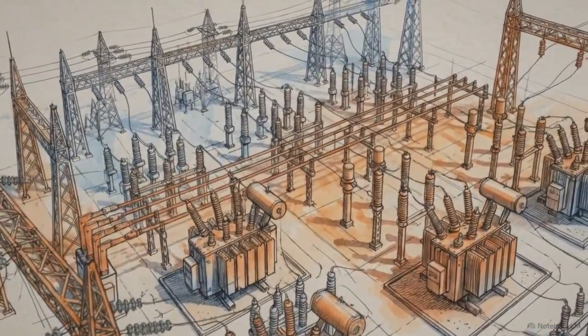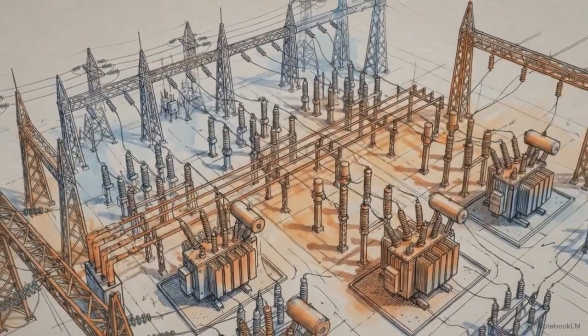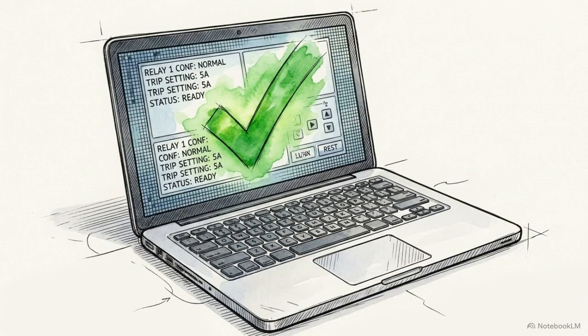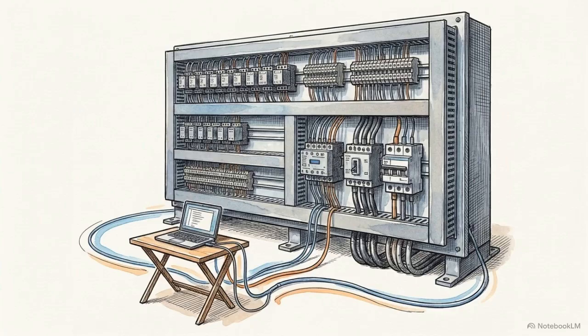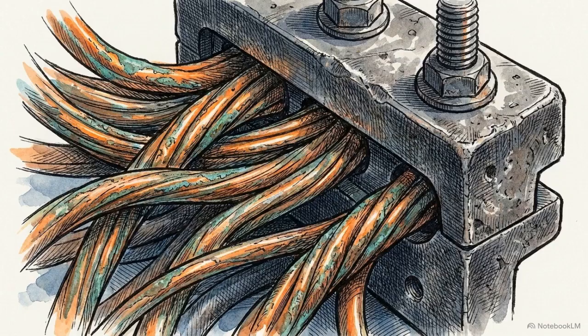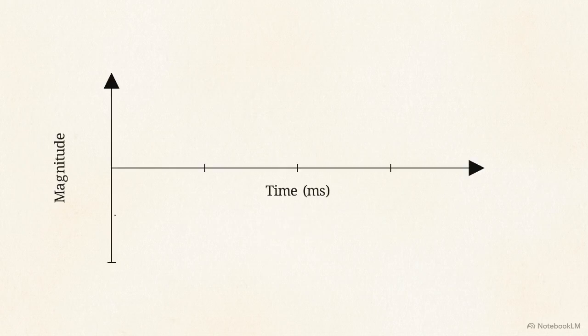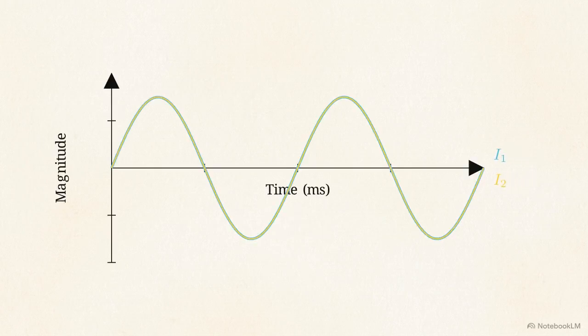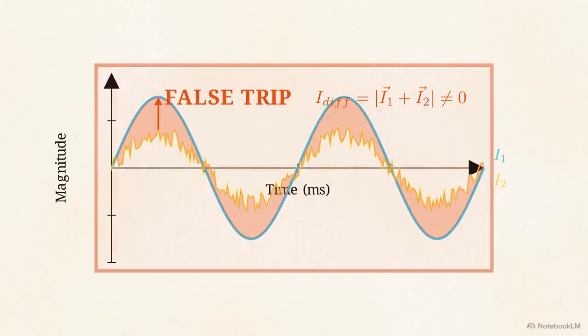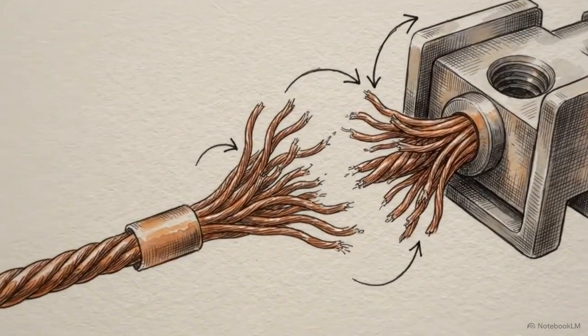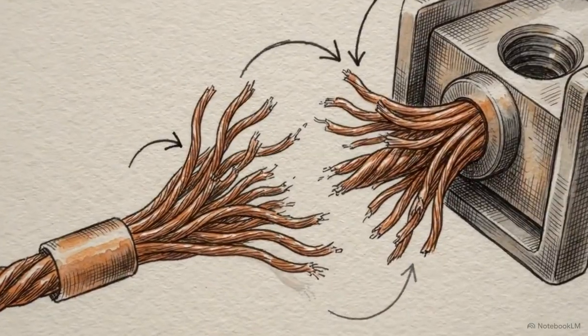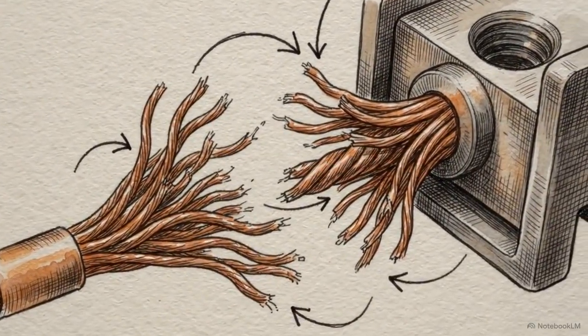cascading hardware failure. A successful secondary injection test confirms the digital logic is correct, but a passed software test does not mean the panel is ready. The physical layer, copper wires, terminal blocks, and mechanical coils, will eventually subvert the code. Ghost currents are a common edge case. When an otherwise perfect relay calculates incorrect vector math, the cause is rarely a firmware glitch.